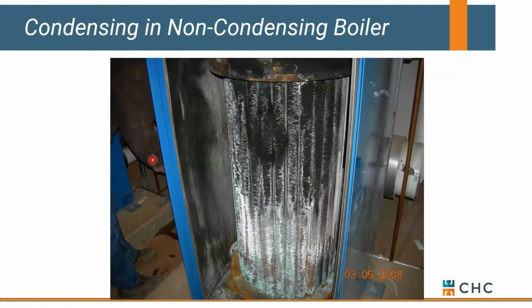Now, what happens if we condense in a non-condensing boiler? In this case, you've got a copper fin boiler that was run for 4 years in a condensing mode, meaning low temperatures in the school district. And you can see all the acid etching that's occurring on the copper fin heat exchanger in this case. After 4 years, they eventually ended up with a failure. We've seen them fail in 6 months, in 9 months. Typically, it's less than a year. So in this case, 4 years is actually pretty good service. The shame of it, there's really easy ways to protect it, and we just talked about those. Either circuit setters or a self-contained three-way valve.